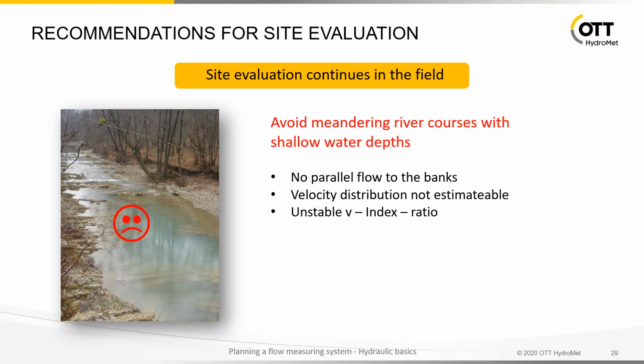Avoid meandering river courses with shallow water depths. So this is a very shallow water here. You see the ground in this case. You see the water is coming from here and goes always to and fro in different directions, so you have cross flow because the river bed geometry is not uniform. So no parallel flow to the bank. Velocity distribution is not predictable, and we have unstable velocity index ratios.